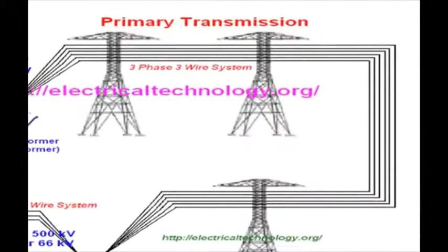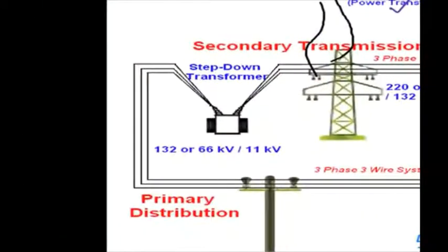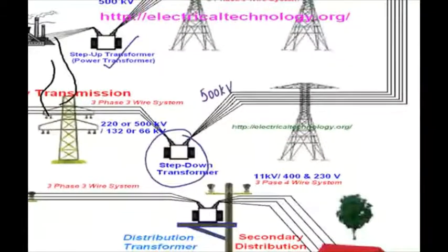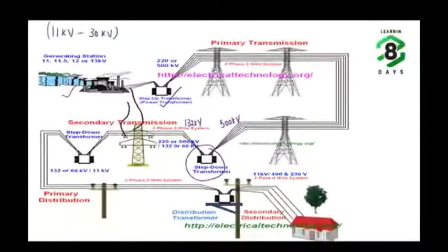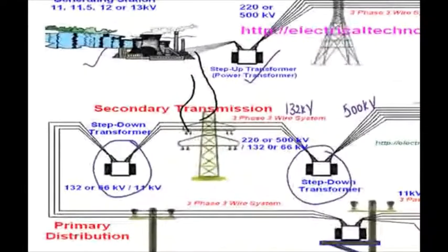Again there will be a step down transformer, that is a substation where the voltage is stepped down from high voltage to medium voltage. Usually the step down occurs, suppose this is a 500 kV line, so it steps down, let us say, from 500 kV to say 132 kV. Again the secondary transmission occurs from 132 kV. Again in the vicinity of any town or a city, there would be a stepping down transformer housed in the substation. Suppose here it is stepping down the voltage from 132 kV on HT side to 33 kV or 11 kV, any voltage.